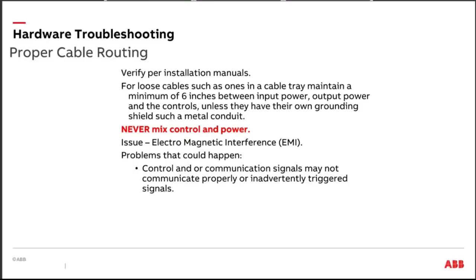They had so much inductive coupling into the control section that you could walk up to the drive on the motor control center side, hit the stop button, and the keypad would clear and the motor would stop. When you took your finger off the stop button, with 3-wire control, the drive would start back up. There was enough induced current there to actually keep the control circuits hot all the time. It was a mess and we had to fix it, okay?